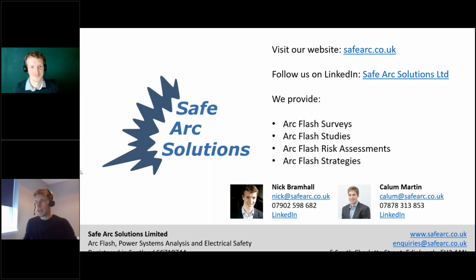And can GFCI or ELCB, so ground fault protection, prevent arc flashes from occurring? Another good question. Really, it's your overcurrent protection that is your primary protection against this, because arc flash is a highly dynamic phenomenon, which can evolve. The type of fault that it can manifest as can develop as an arc flash continues, and as it gets worse and does more and more equipment damage. What we tend to find is that it maybe starts off as a phase-to-phase fault, but rapidly spreads to become a three-phase fault, and then might find a path to earth as more damage is done. So primarily, you're looking for the fault current flow that's associated with an arc flash.